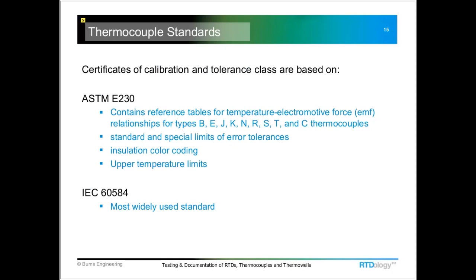With thermocouples, there really is not a whole lot of documentation that goes with them. There's a standard that would drive a document, basically a kind of verification document that would say that the thermocouple has been tested and found to be one of the basic types of thermocouples. These different types just have a different temperature-voltage relationship and temperature capability. So the verification document would just say, yes, it's a type K, and it falls within this error tolerance band, whether it's special limits or standard limits.